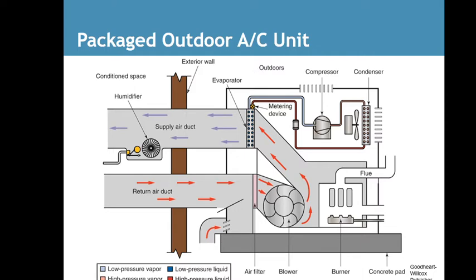And there are some odd items on here that you won't normally see in a home system, like the humidifier in the top left-hand section. This unit actually spins water droplets off that wheel and they get picked up by the supply air and taken through the ductwork into the living space to add a little bit of humidification. Now you won't find that in Florida because we have plenty of humidity, but remember, air conditioning takes out humidity, so depending on how well that unit works and how long it runs, you could take a lot of humidity out of the air. But normally you'll find these out in the West in desert climates where, during the summer, you might be down to 3% humidity.